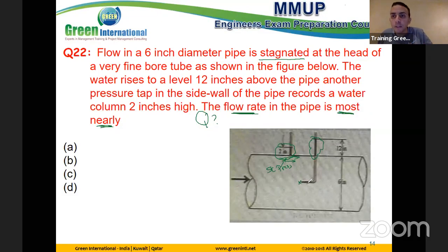The velocity stopped, the energy going inside is transferred to head. So this head is related to what? Related to static by default, same like this 2 inch. I have 2 inch here, same like this 2 inch. It means this one has static and this one also has static by default for the normal flow, but plus static is also added the dynamic part.